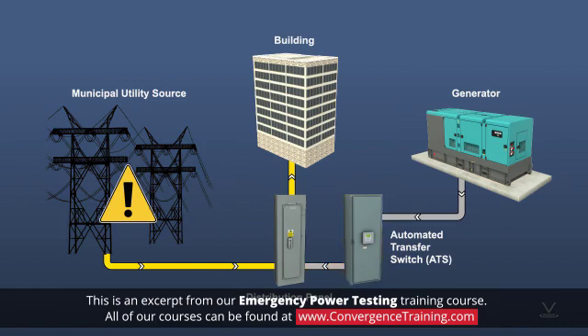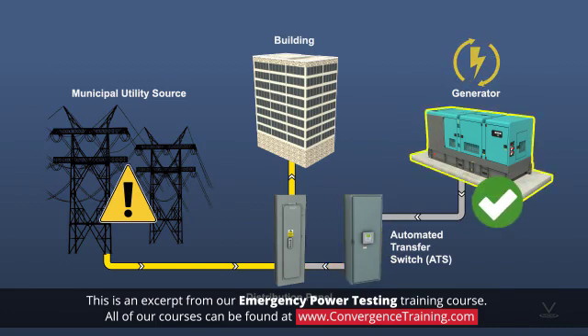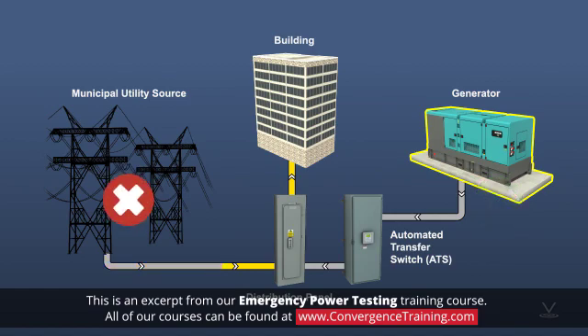1. The generator will start and its voltage is allowed to stabilize — 5 seconds. 2. The ATS will disconnect the utility power from the load. 3. The ATS will connect the generator power to the load.